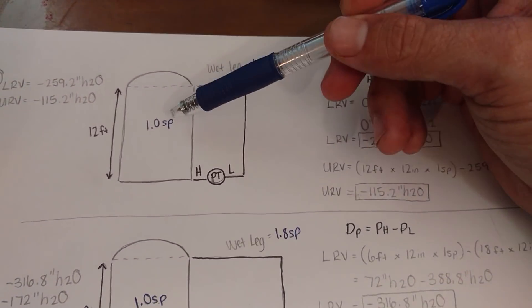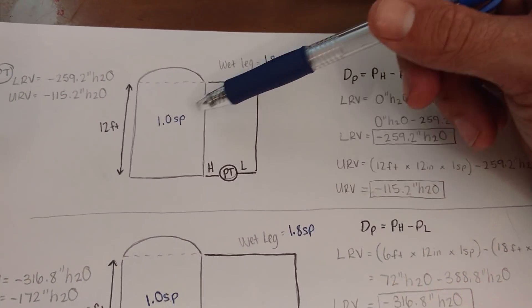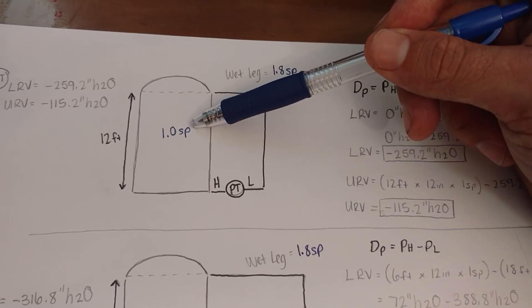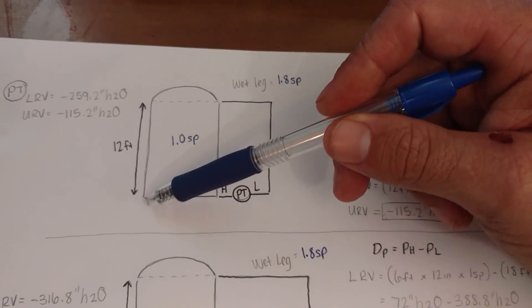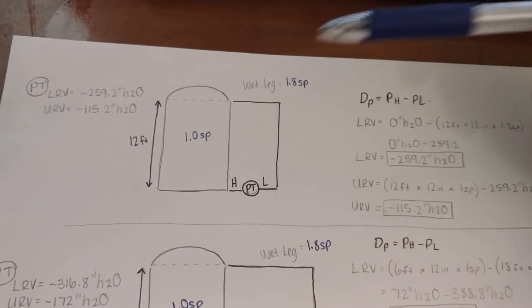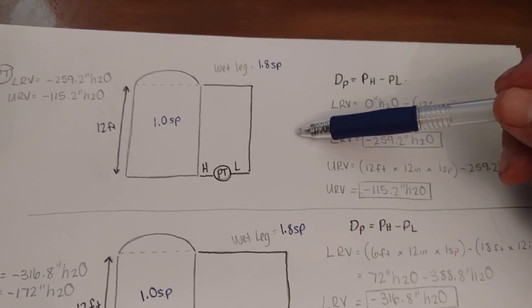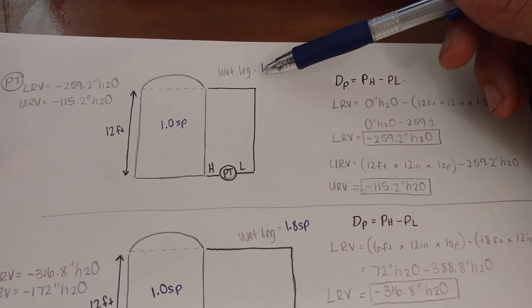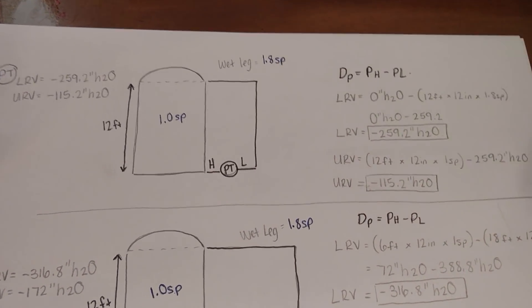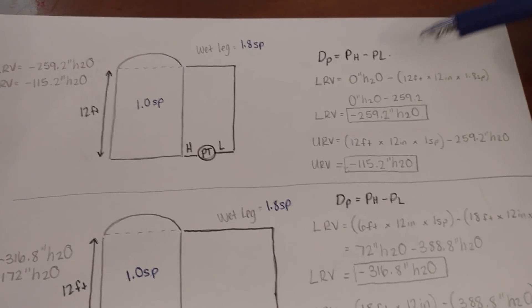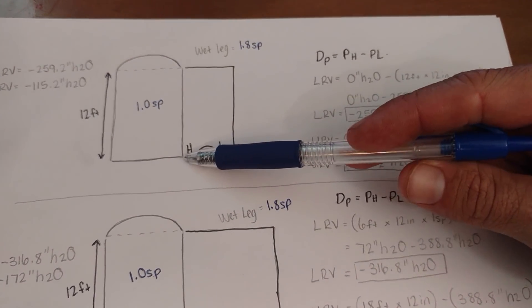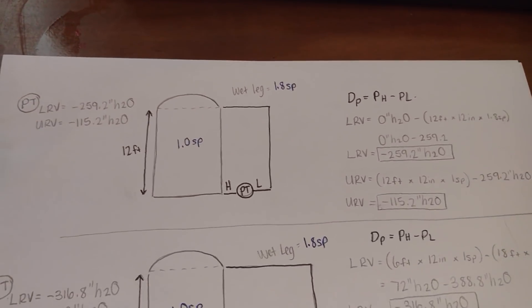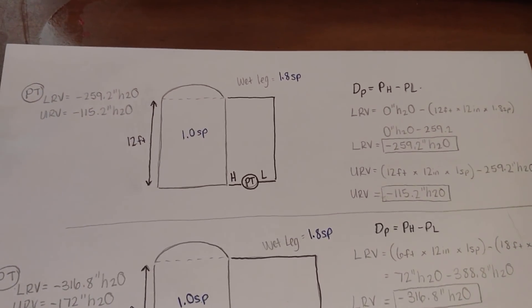In this situation, we have a tank. It's filled with water — we know that because the specific gravity is 1 — and it's 12 feet high. We have a wet leg over here that has a specific gravity of 1.8, so we know it's more dense than water. Here's our pressure transmitter, here's our high side, here's our low side. Let's find the upper range value and the lower range value.